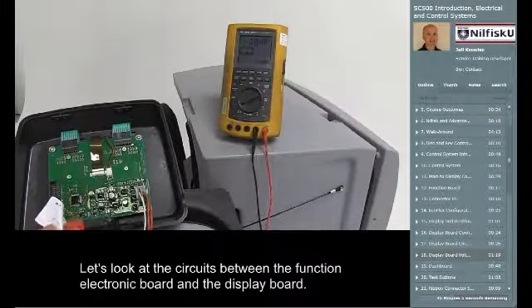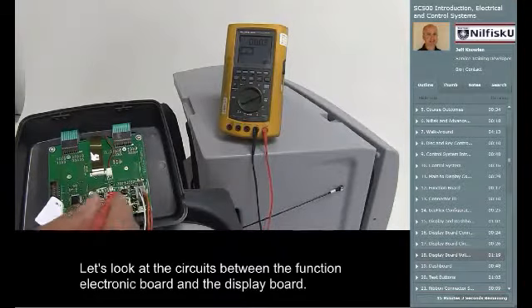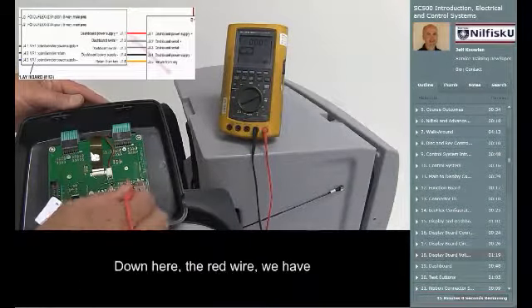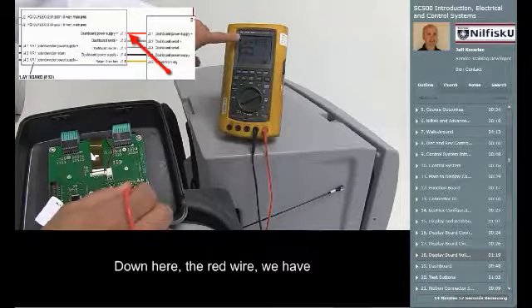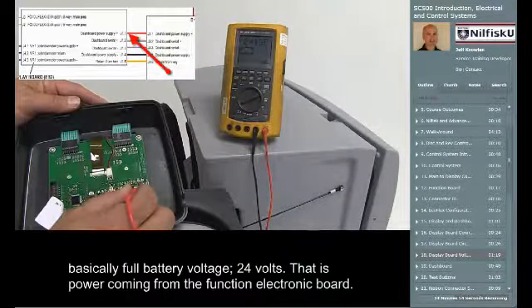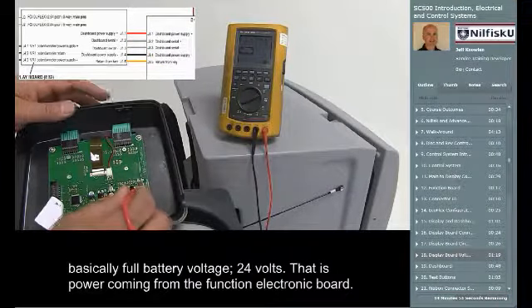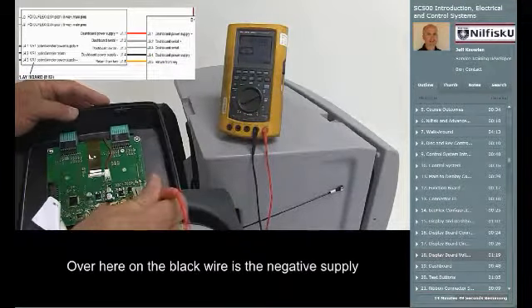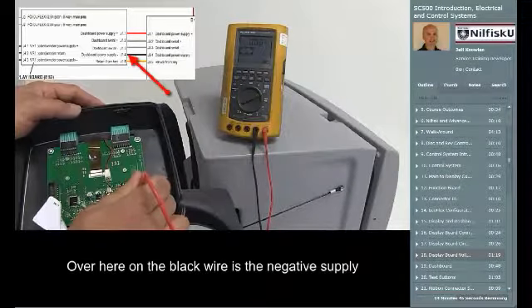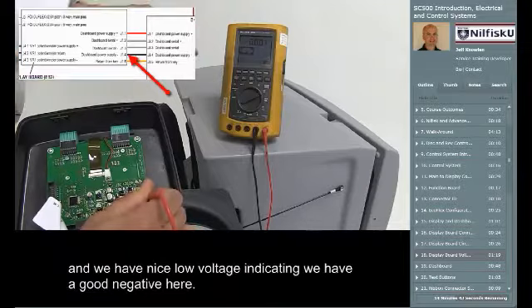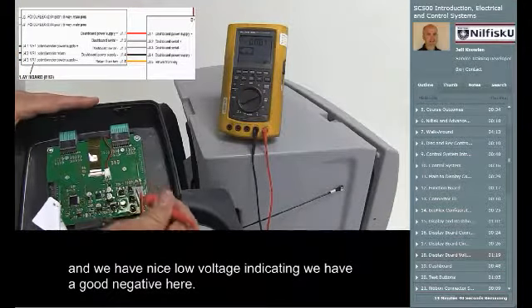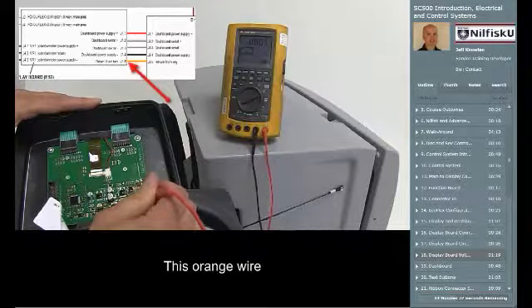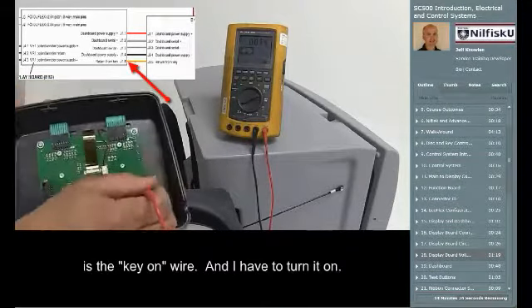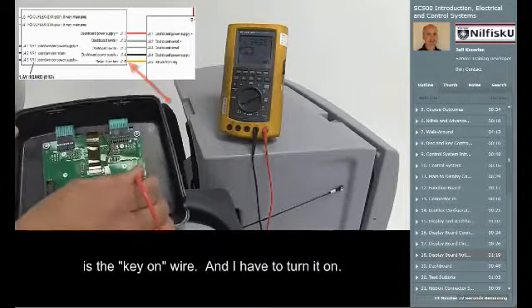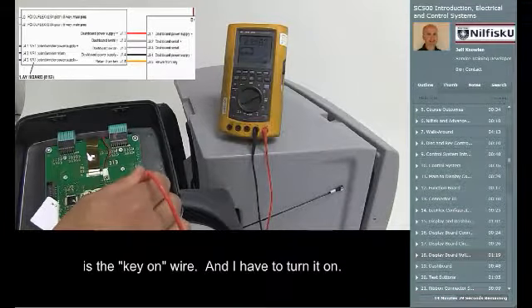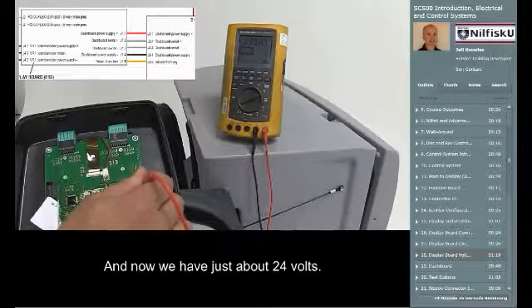Let's look at the circuits between the function electronic board and the display board. Down here, the red wire, we have basically full battery voltage, 24 volts. That is power coming from the function electronic board. Over here on the black wire is the negative supply. And we have nice low voltage indicating we have a good negative here. This orange wire is the key on wire, and I have to turn it on. And now we have just about 24 volts.